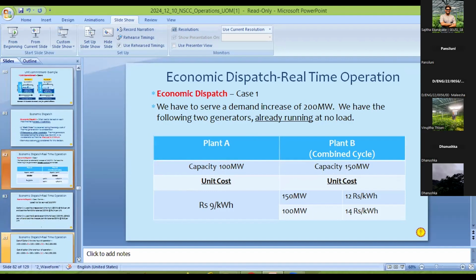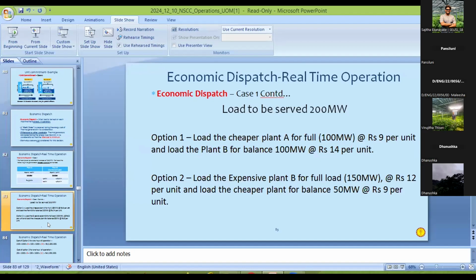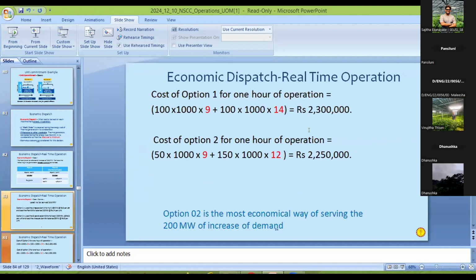So you can do the calculation and see which option is best. These are the two options I told you. Option one is loading plant A at 100 megawatt, then taking the balance from plant B. Option two is operating the combined cycle plant at its full load, with the remaining 50 megawatt taken from plant A. If you do the calculation, these will be the answers.